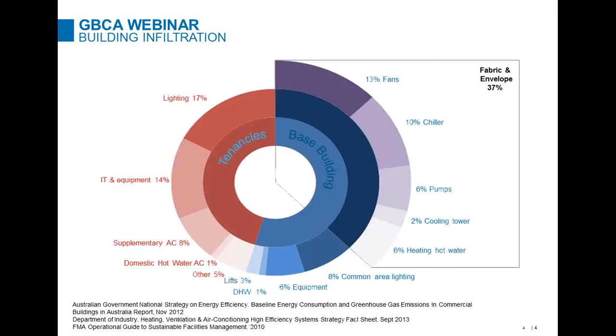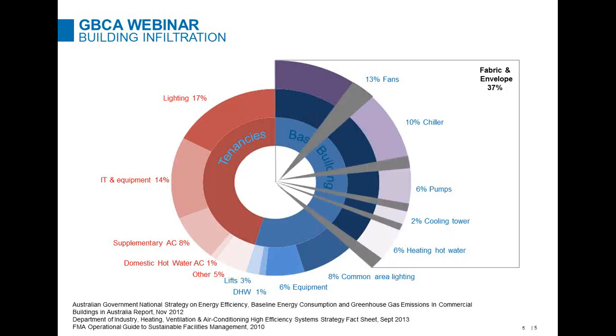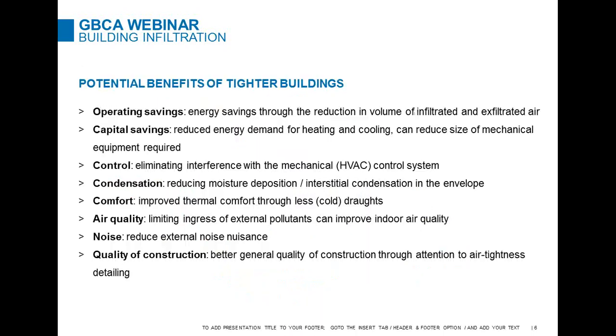Still a significant saving across a commercial building when you think about the next slide, these nested pie charts of the split in energy of a commercial building between the base building energy consumption and the tenancy. The area highlighted shows that which might be attributable, in terms of the services energy, to the building fabric. So obviously if we have a better building fabric, better insulation, better glazing, better sealing, we're going to use less fan power. Our chiller's going to have to work less hard. Our pump's going to have to work less hard. Our cooling tower's not rejecting as much heat, and we're not doing as much heating in winter with our boilers. So we could nibble away at various parts of the energy consumption of the services, and we might conservatively say that we could achieve a 7.5% total building energy saving by improving the air tightness.